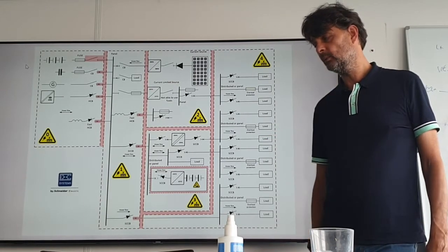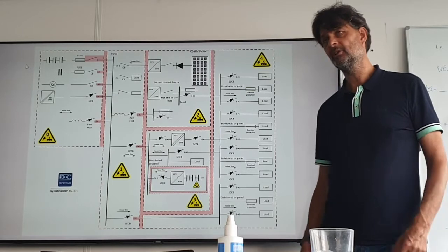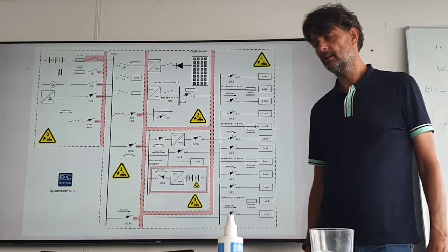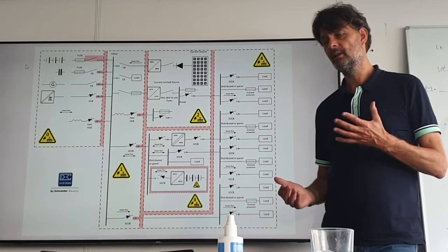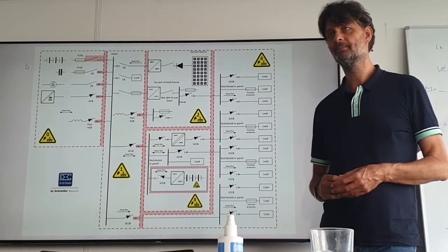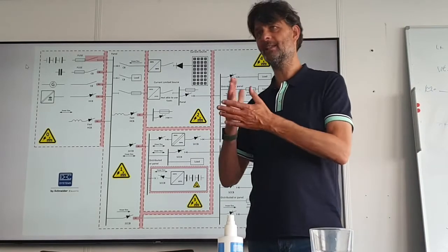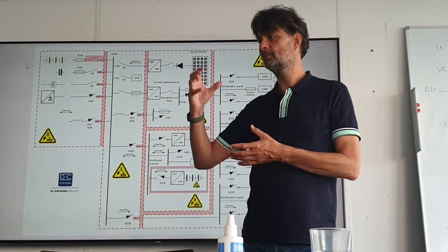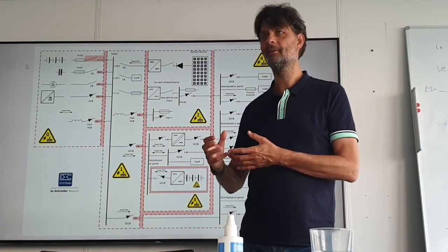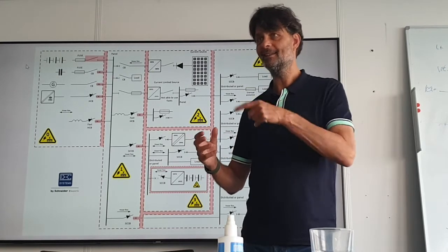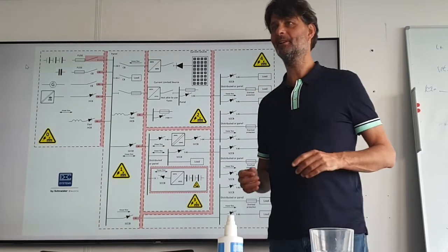And then one company got a project from the municipality, where the municipality asked the inspector, is DC as safe as AC? And the funny thing was that they made connection faults in the streetlights. So one of the poles was not earth connected, and they found it.